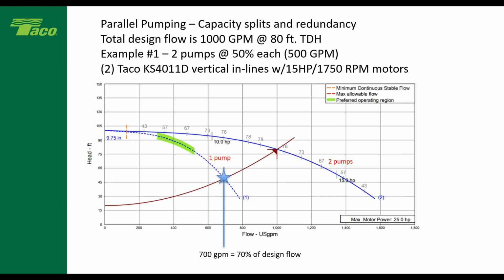So if I look at a KS 4011D vertical inline pump, sized for 1,000 GPM at 80 feet of head. If I put two pumps in, each sized for 50%, so I'm doing 500 GPM per pump, I've got 70% of redundancy. Okay, that's what that pump is going to deliver if it's just one pump and it runs out to full speed. That's what it's going to deliver.